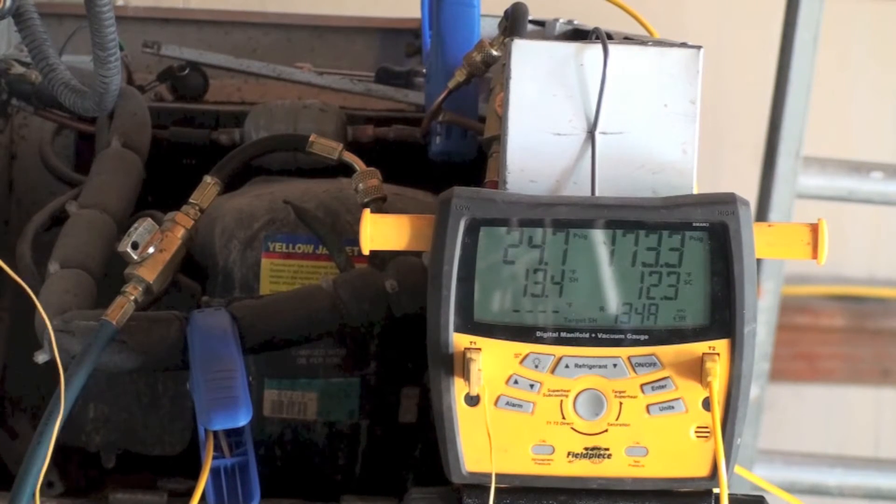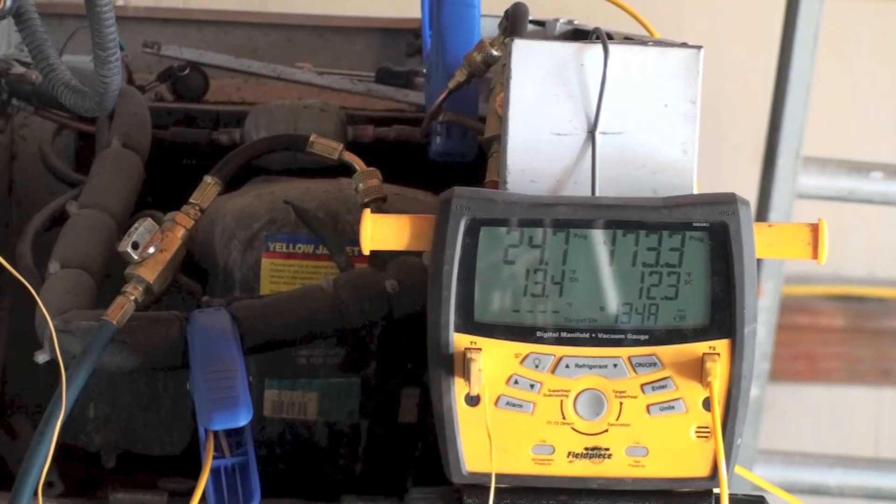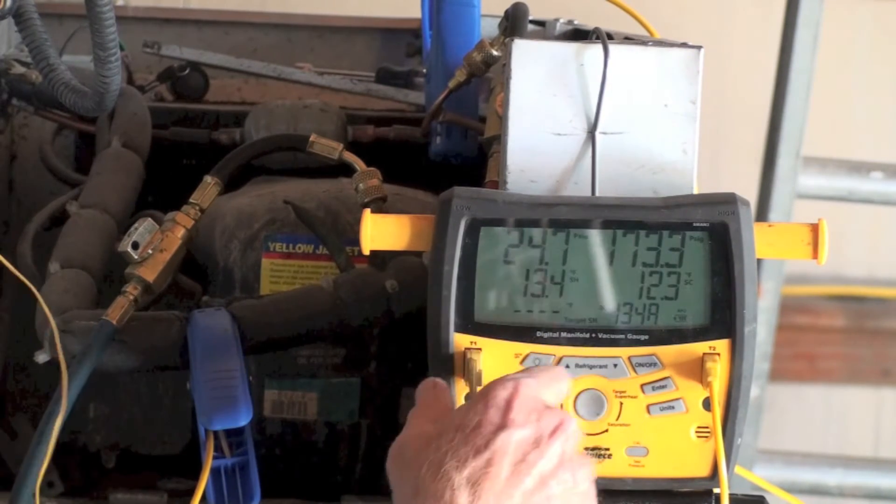Right now, I'm reading off of the inside probe and we've got 13.4 superheat.